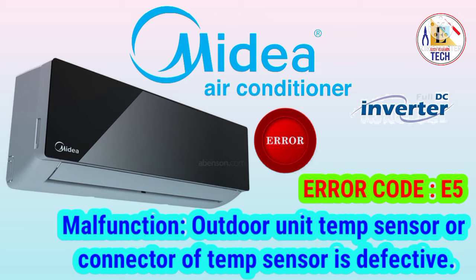if it is cut or if it is damaged or not. If it is not cut or not damaged, then you have to check the output supply from your outdoor PCB. If the output supply is not good, then you have to change the outdoor PCB and you will get the solution for the error E5.